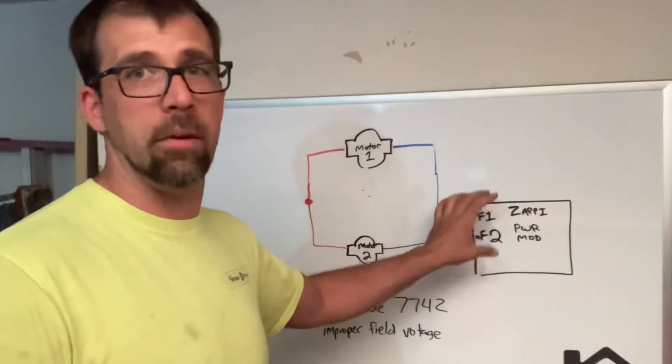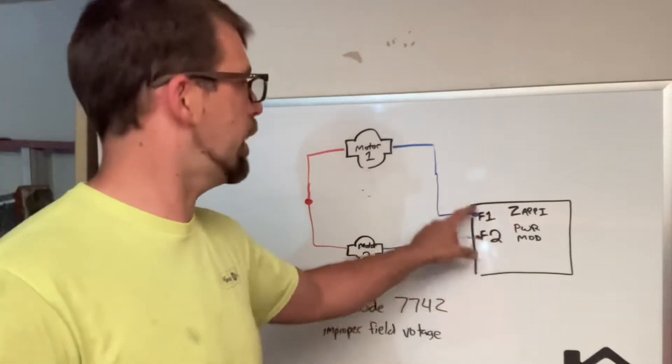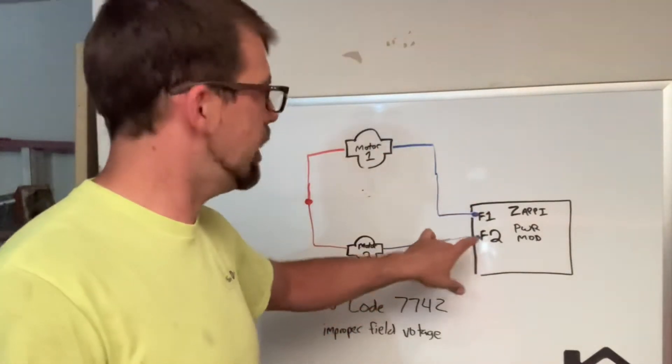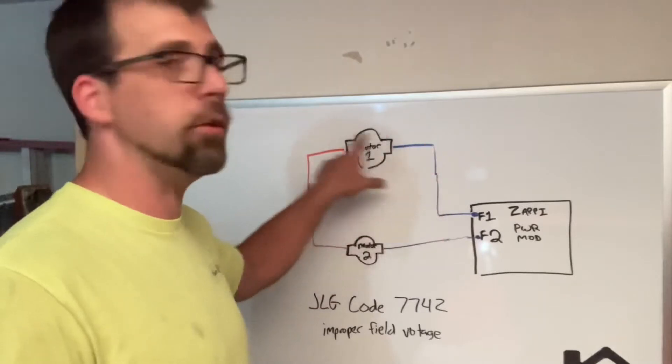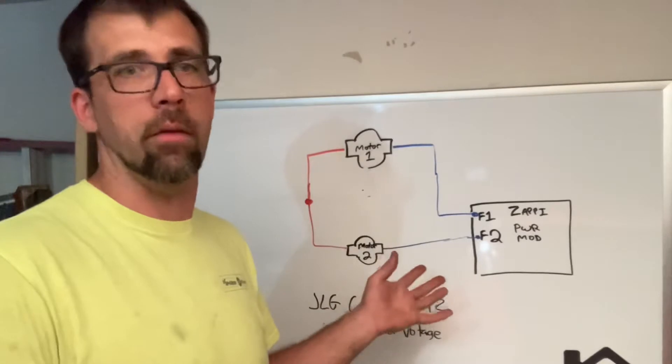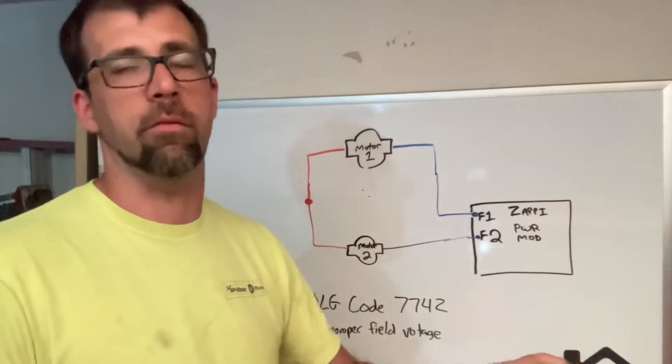F1 and F2 terminals on the ZAPI are labeled, though both wires will actually be blue. There's the illustration — I've used blue to help simplify that. What happens is when that signal doesn't make it back because of some kind of a fault, it'll set this code, and of course it disables any function from the machine.